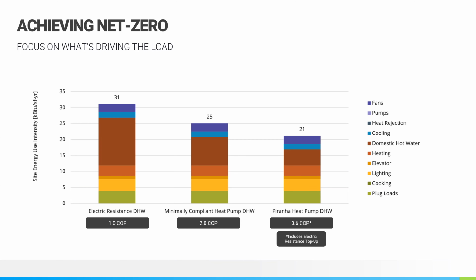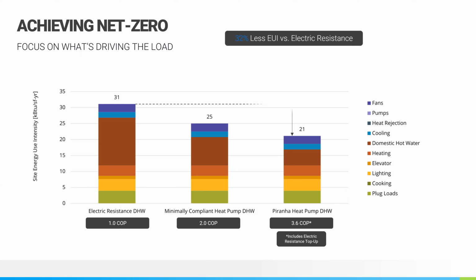When they ran the energy analysis comparing three different options for creating domestic hot water electrically, versus electric resistance there was about a 32% reduction in site energy use intensity, which is basically the energy use divided by the square footage over the entire year.